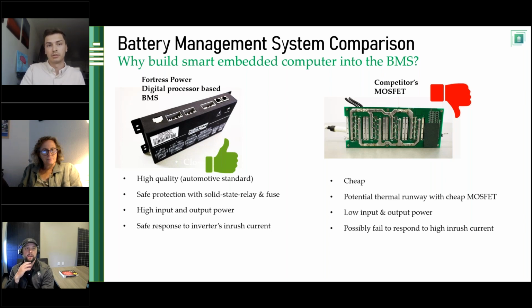What are your thoughts? I'm not going to disagree, it certainly is the most important part. There's a number of battery cell manufacturers out there that make a relatively similar standard cell, so you want a high quality cell because the quality assurance associated with that is held to a certain standard. For the most part it's still the same chemistry, so you get similar life out of the cells. The problem is with quality assurance, a cell failure can take out a battery, but if you don't have a good BMS and it fails, it's going to destroy everything. The battery management system is by far one of the most important aspects of the system.